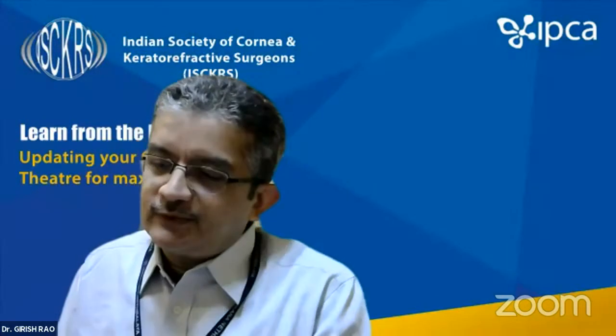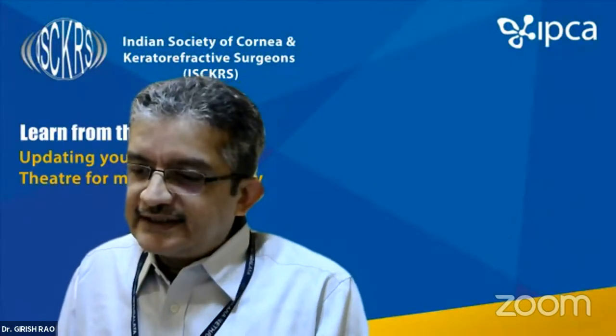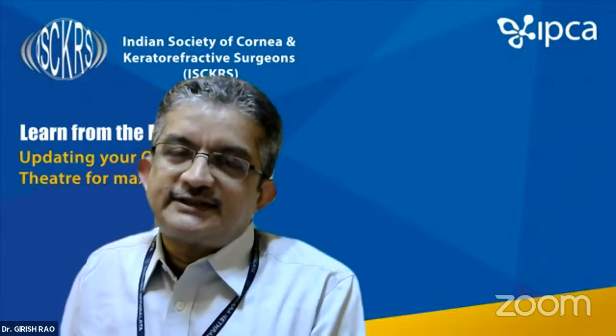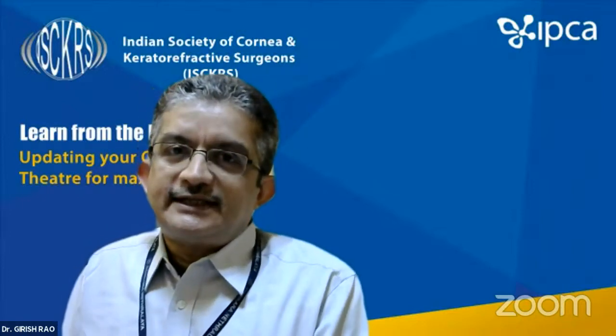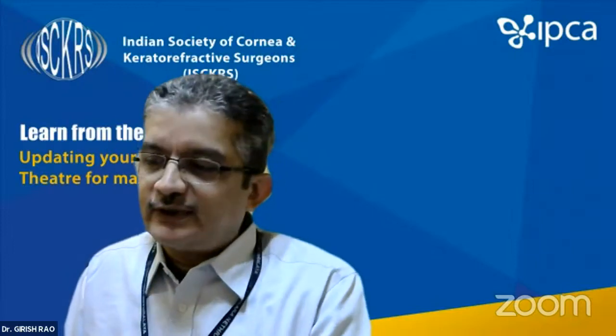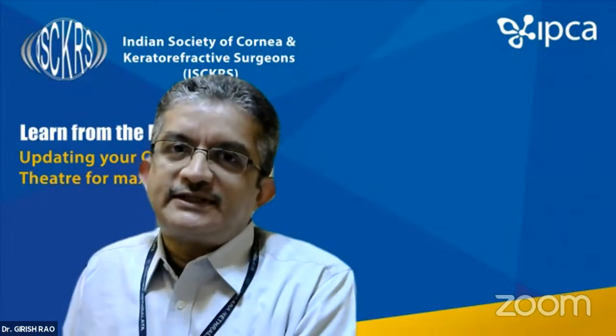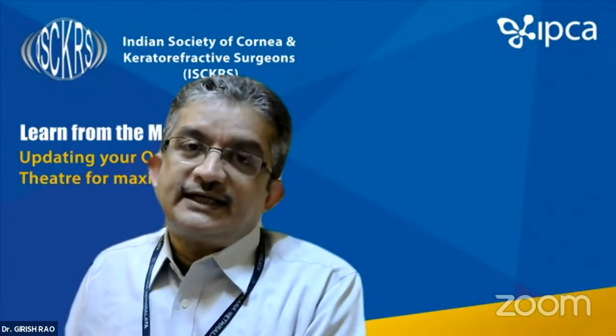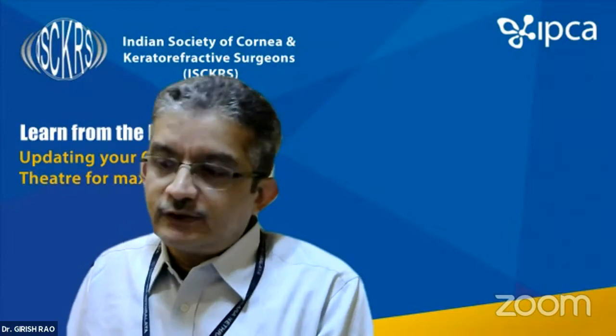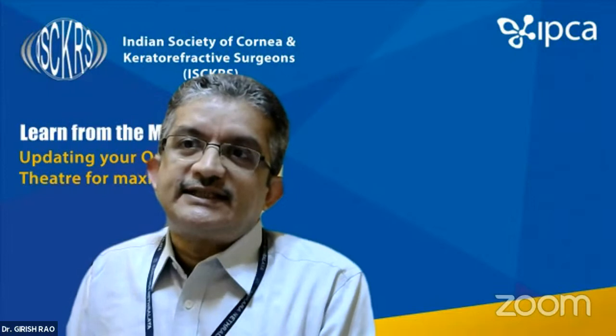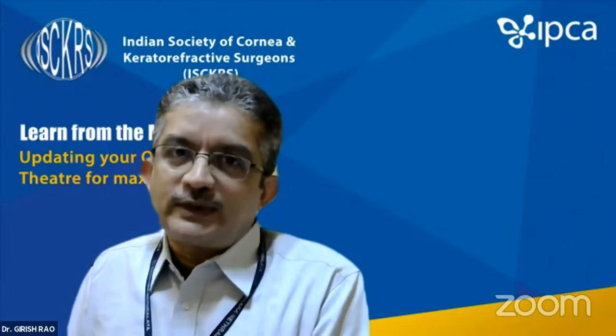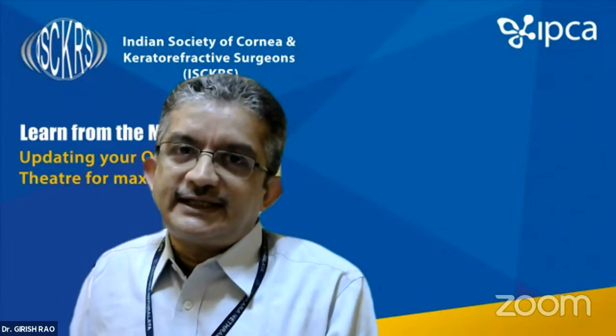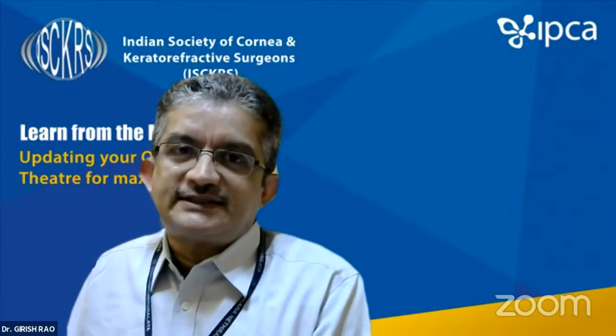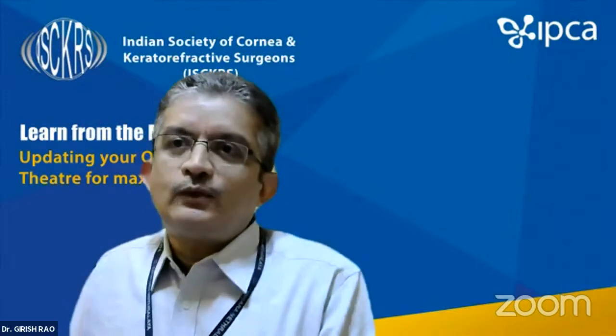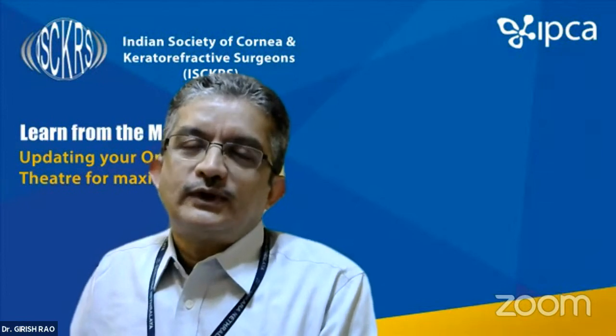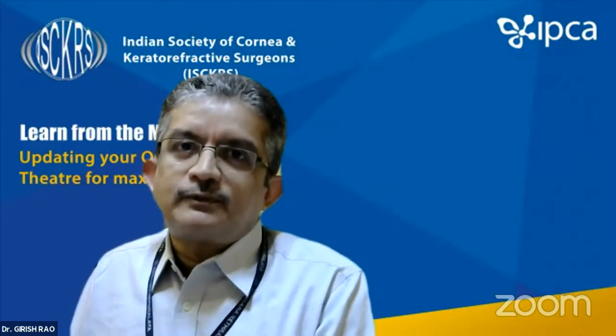I just wanted to highlight some of the OT considerations in a single theater practice or a single person practice, how it differs from what a standard NABH operation theater would require. So you have now showed a very beautiful video of an NABH compliant OT with a separate single AHU for each OT, which is the most ideal. Though NABH right now doesn't insist that there should be a single AHU for a single OT. As per the 2018 guidelines, and that's more because of the concerns of most of the hospitals in India. So they do allow for an AHU to cater to more than one operation theater, provided you have a backup.